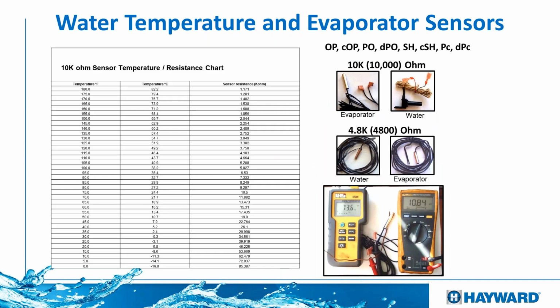For the water temperature sensor and evaporator sensor, the way we can check them to make sure they're good, in case we get one of these codes like OP, COP, PO, DPO, etc., is to check the ohms on the sensor. We disconnect the sensor and check for ohms, and depending on the temperature of the water, that will determine how many ohms we have. If we're not close to that number, the sensor is definitely bad, or if it's open, definitely bad. As you can see in this chart, if we have an 85-degree Fahrenheit temperature, we should get a reading of 8.249 kilohms. If we're not close to that, we definitely have a bad sensor. And if it's open, definitely a bad sensor.